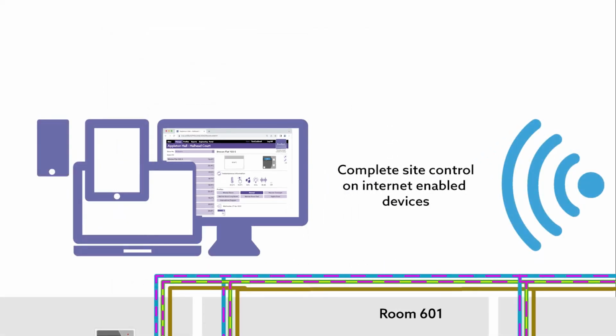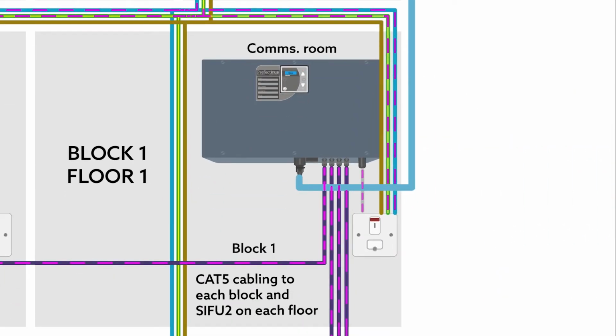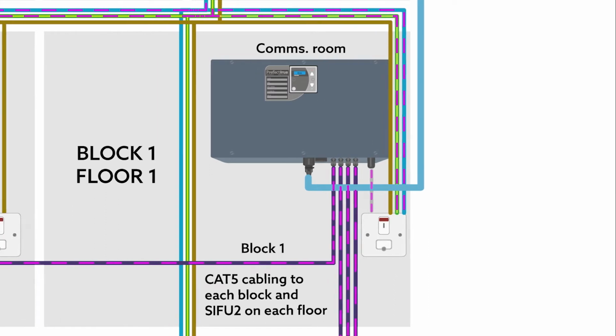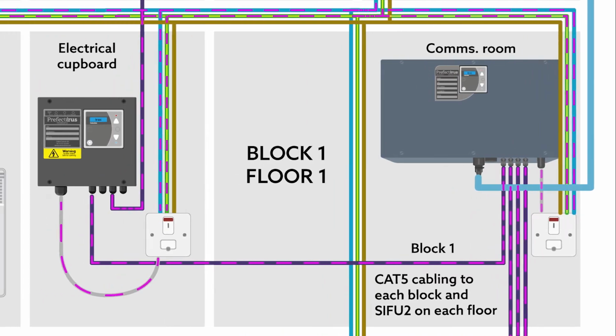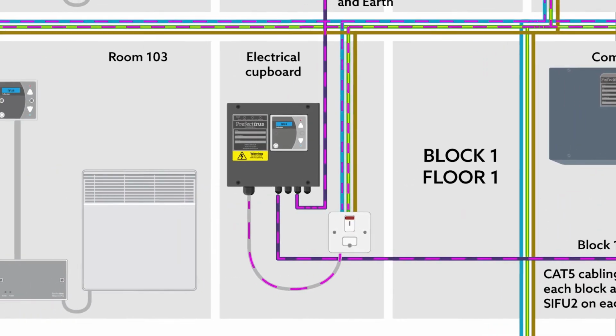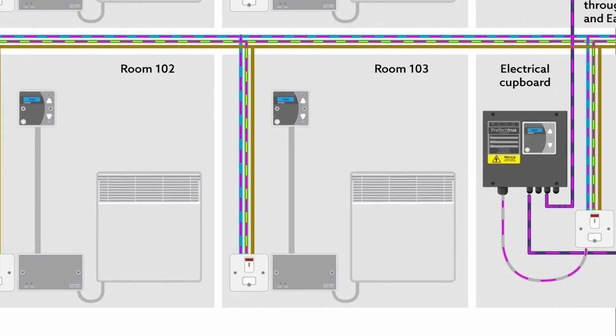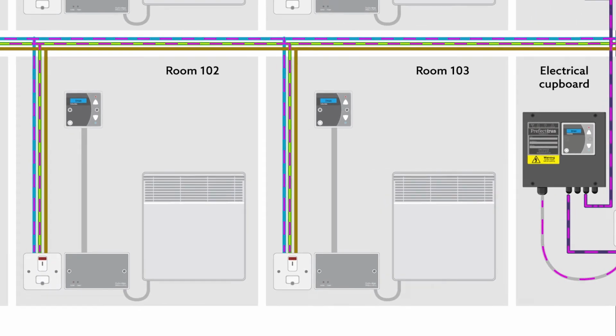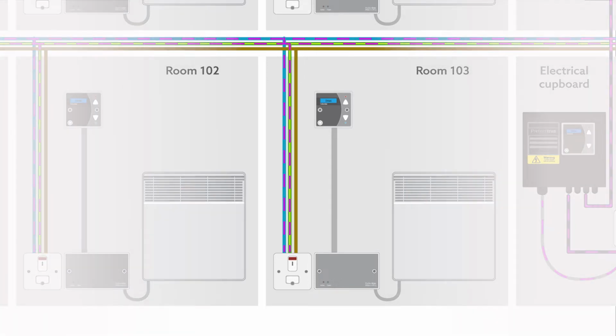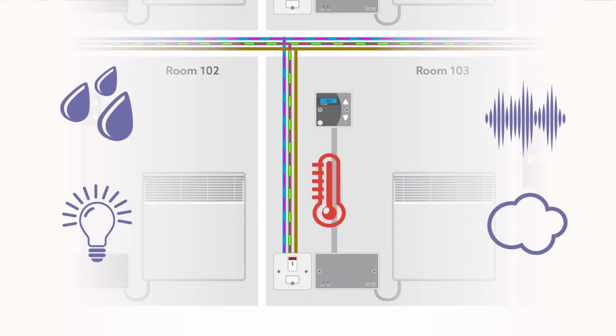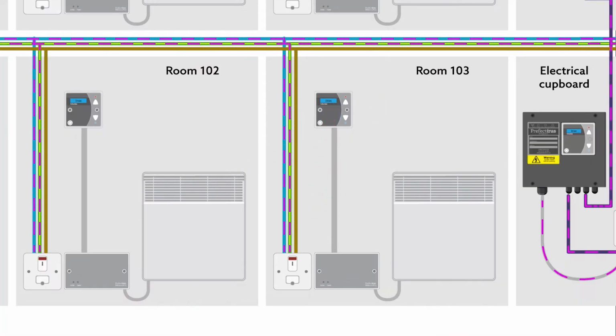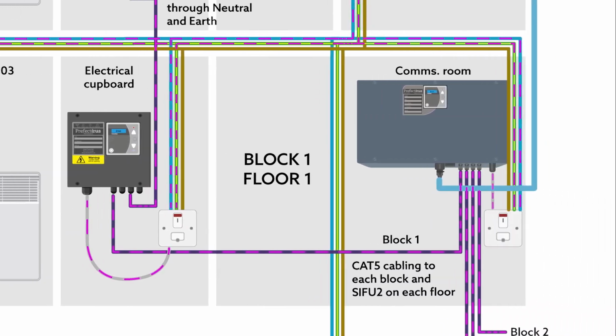This is how Irus is configured. The secure portal displays the data collected by the master interface unit. The master interface unit uses either the site's existing data network or Cat5 cable to send and receive data from the secondary interface units, which in turn communicate with the room's control unit using mains-borne signalling. The control unit controls the heat source in the room through a power unit. Modules within the control unit monitor the room's environmental conditions.